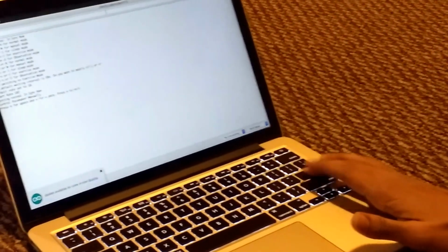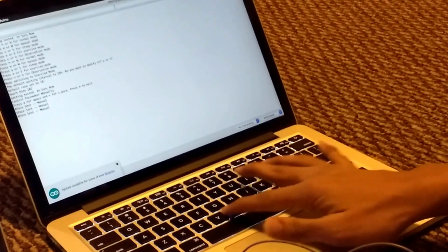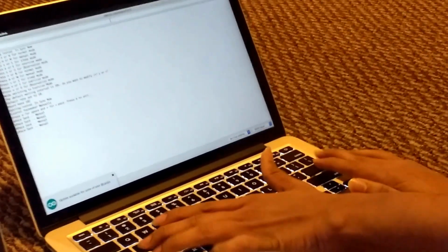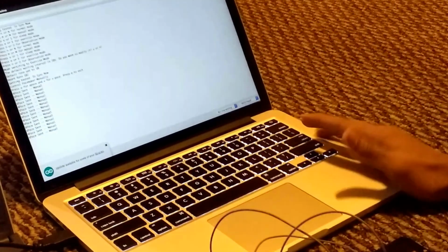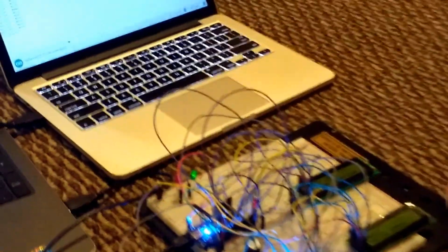Okay. So there's A, this is V, this is A, this is V. In this manner, we are manually controlling our pacemaker to control the heart. Now I am exiting the manual mode, and it has gone back to the exercise mode.